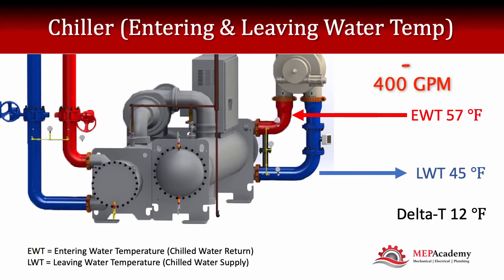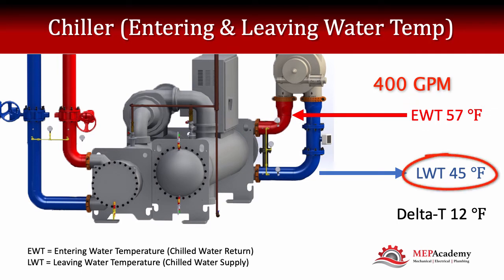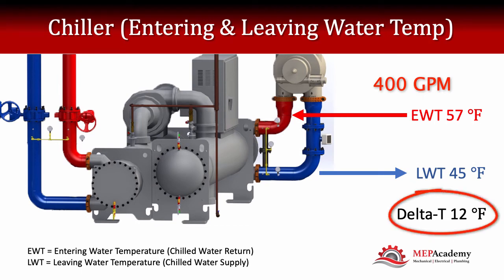Looking at our chiller, we have 400 GPM, 57-degree entering water temperature for chilled water return, and 45-degree chilled water supply. That gives us a Delta T — the difference in temperature between supply and return — of 12 degrees. So 400 GPM is our flow, and 12 degrees is our Delta T.